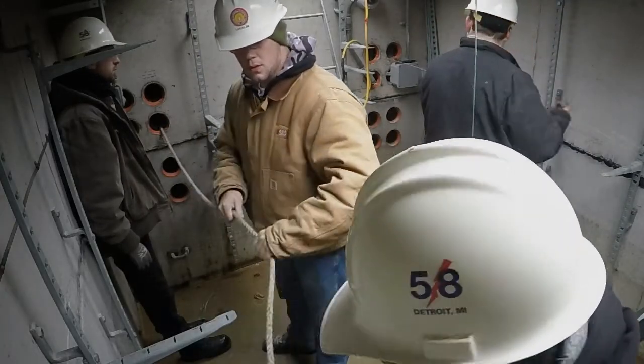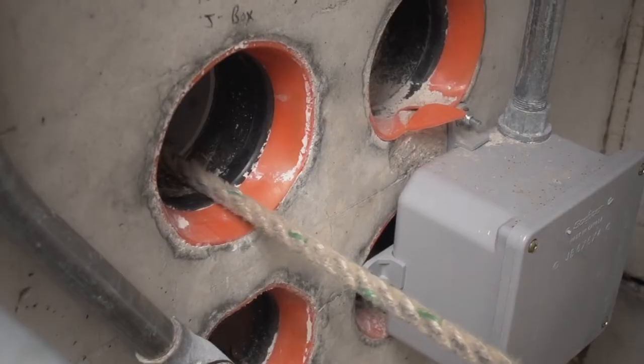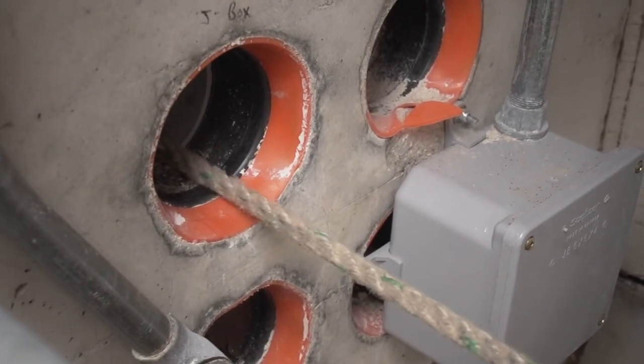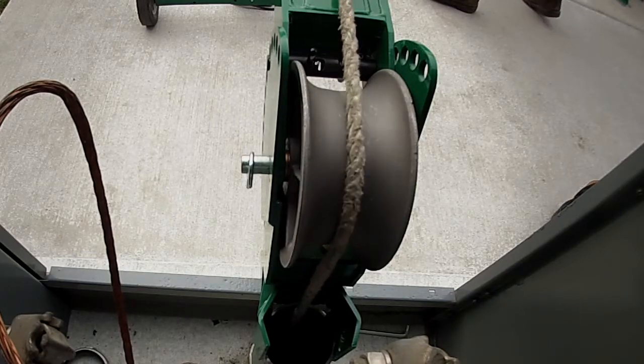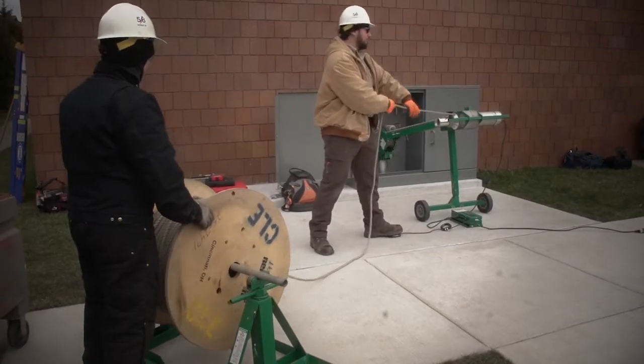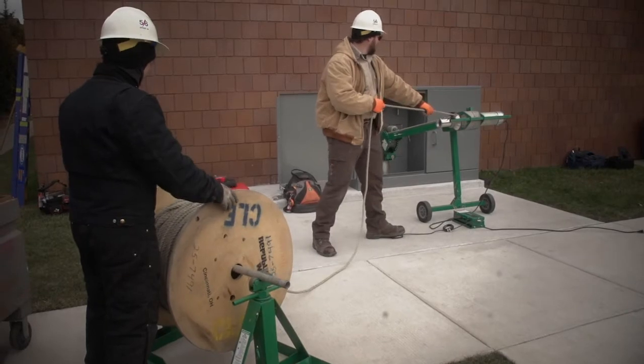On the installation side of a confined space, cable pulling involves a high degree of rigging and extra safety, because ropes under tension can be hazardous. The rigging encompasses all the mechanical setup you have to do just to pull a cable into or through a confined space.